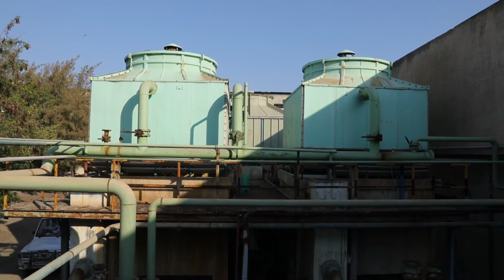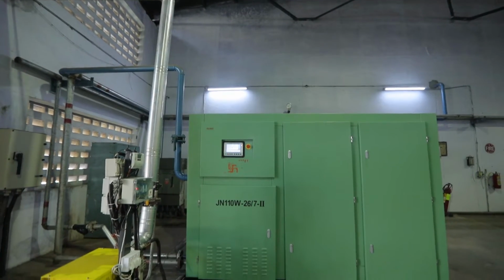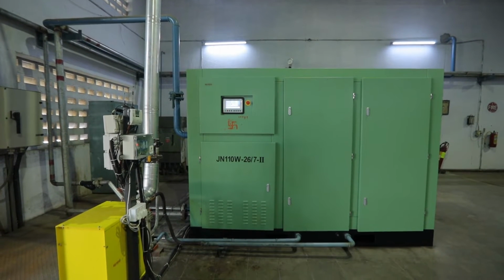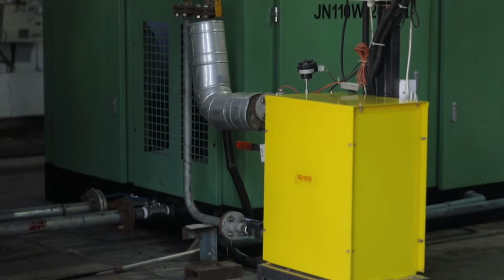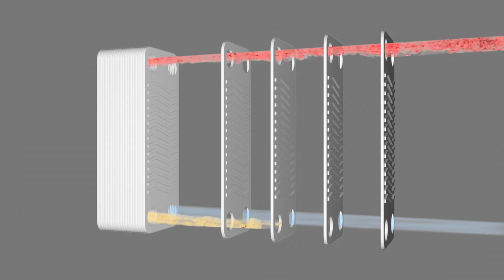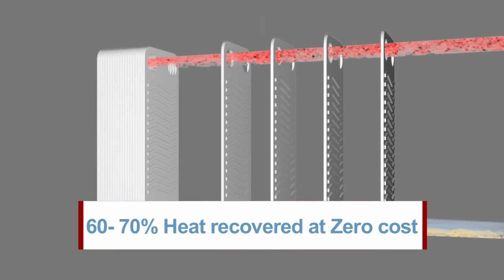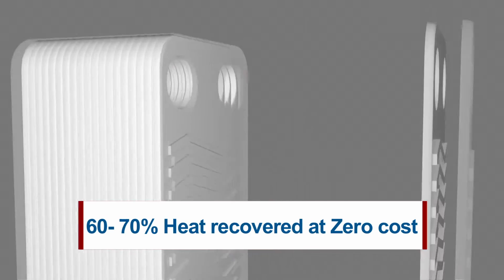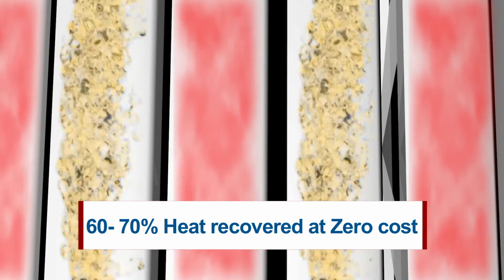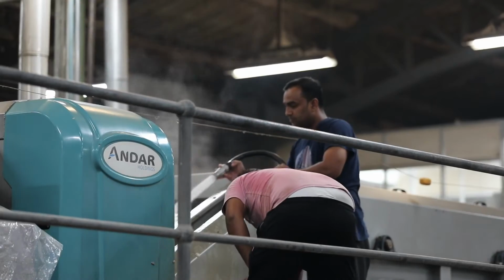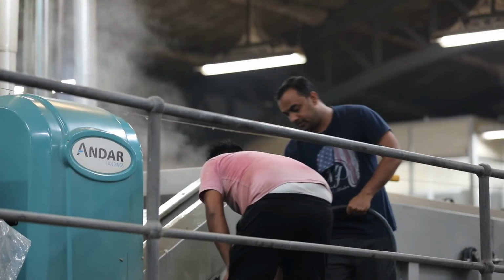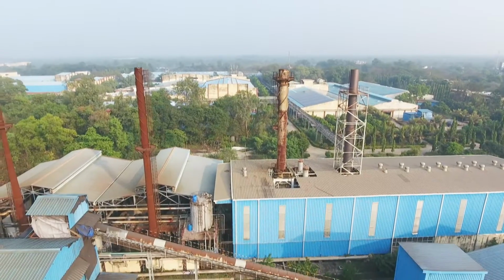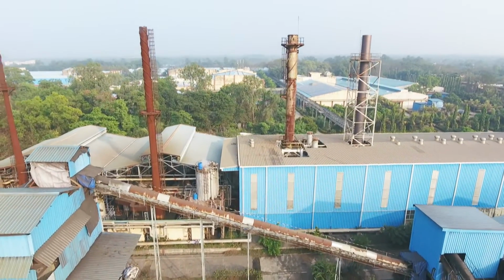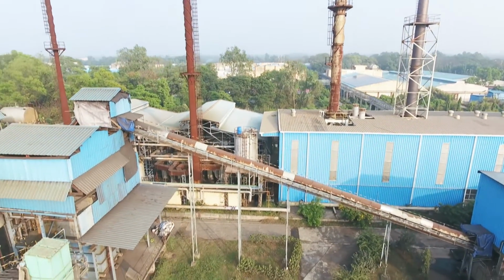Meanwhile, the new technology addresses both these issues as it makes use of this waste heat to heat water. Through the introduction of heat exchanger system, 60 to 70% of heat from the compressor oil gets recovered at zero cost. The hot oil is routed through the heat recovery system and its heat is extracted in the form of hot water, which is further utilized in various other processes. This has resulted in reduced wasteful emissions and has made the process more energy efficient.